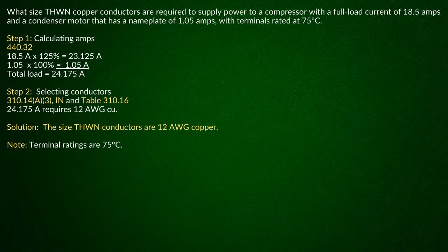Well, here's a good example, and this proves exactly what you were saying, where they got the 24 amps. We had 18.5 amps for the compressor, and then the condenser was 1.05 amps. So if you take the largest, which is 18.5 amps at 125%, that'll give you 23.125. Take the 1.05 for the condenser at 100% and add that up, that'll give you 24.175 amps. If you look at 220.5(B), I'm not over 0.5, so I can just drop down, which is 24 amps, okay? So now all you're going to do is go over and look at Table 310.16, pick up the 75-degree C column, come down. It'll tell you number 12 is good for 25 amps. Therefore, I could install a number 12 conductor here, okay?